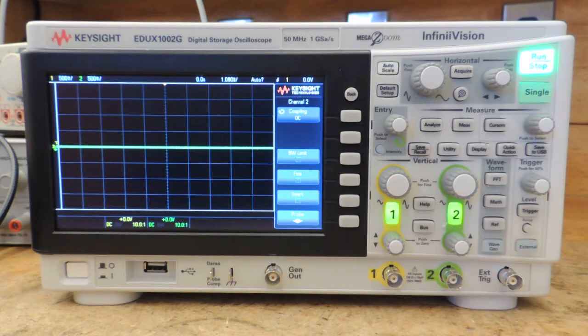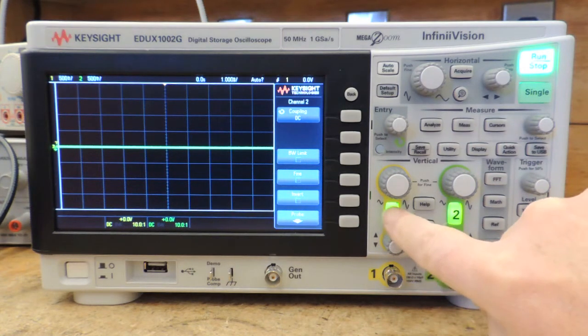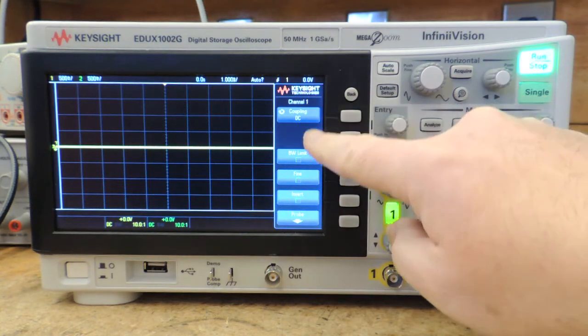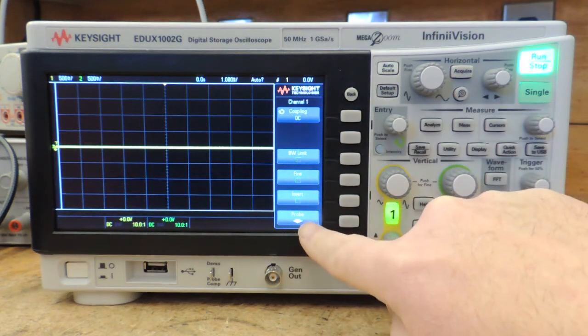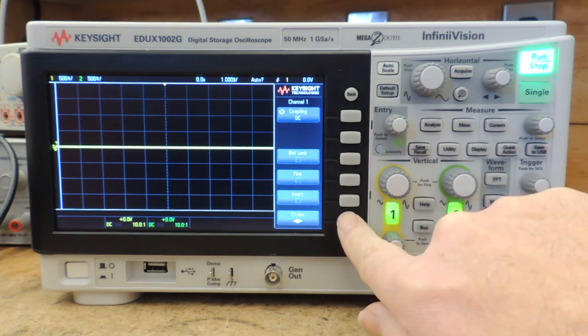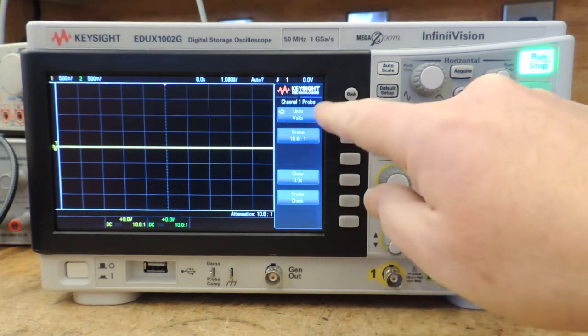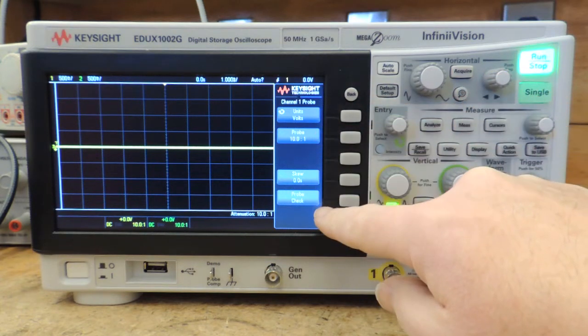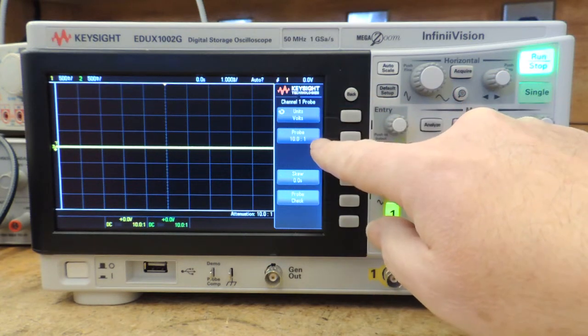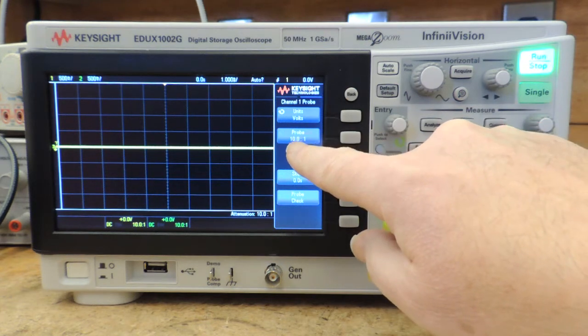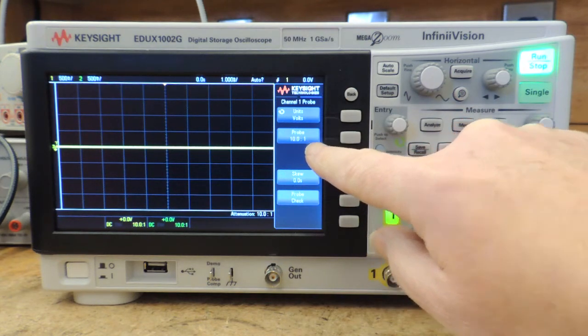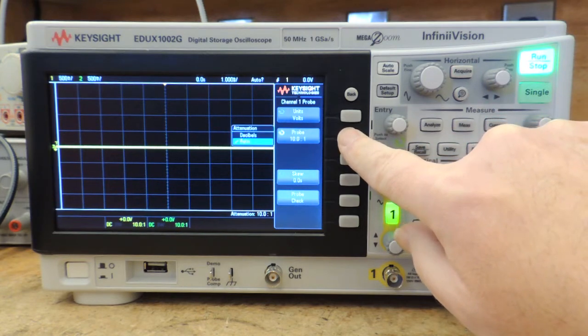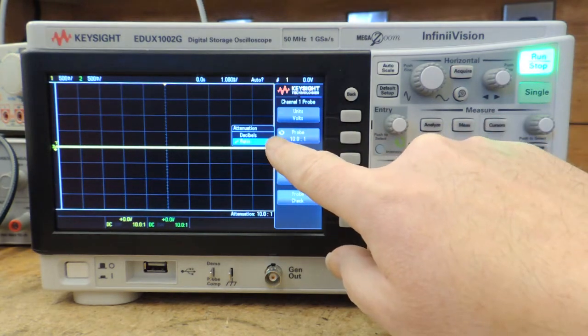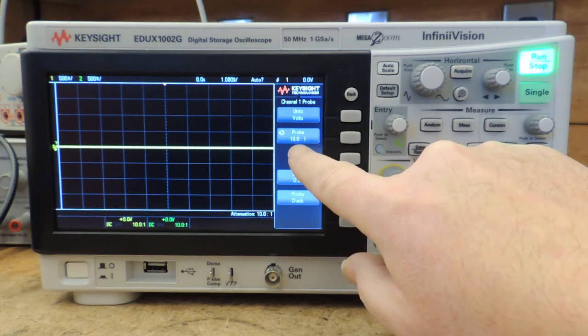So under procedure, step number 3, we're going to set up the probe. So what we're going to do is select channel 1. The channel 1 menu items are displayed. The bottom item is the probe. So we press that menu item, and you can see channel 1 probe has its own menu. We're interested in the second item down, which says probe 10 to 1. So that's a ratio. If you select probe 10 to 1, it can be in decibels or ratio. We want it in ratio.